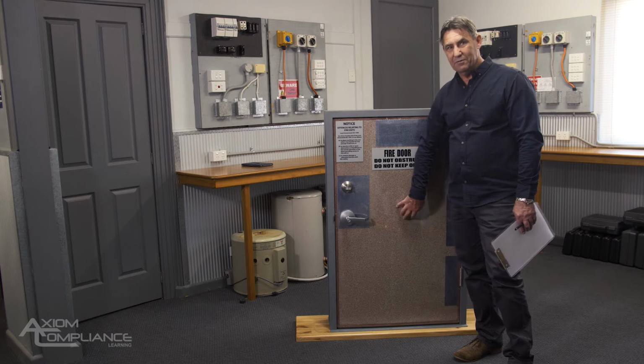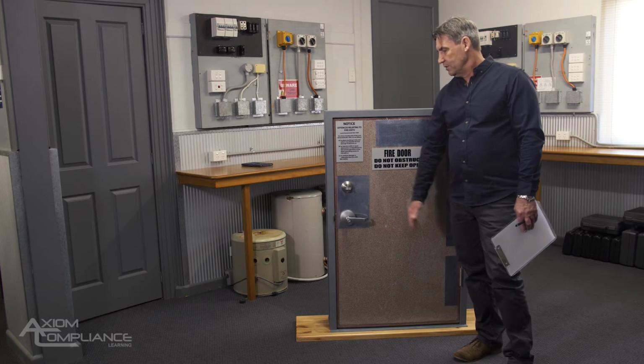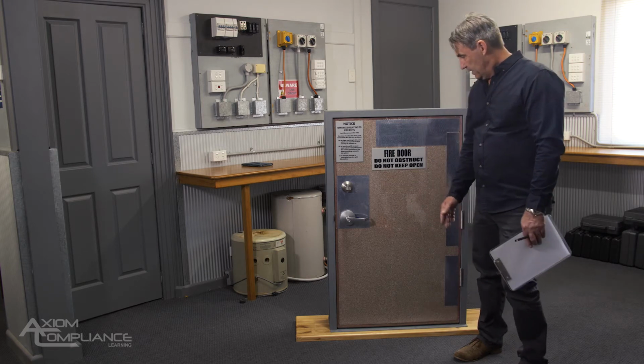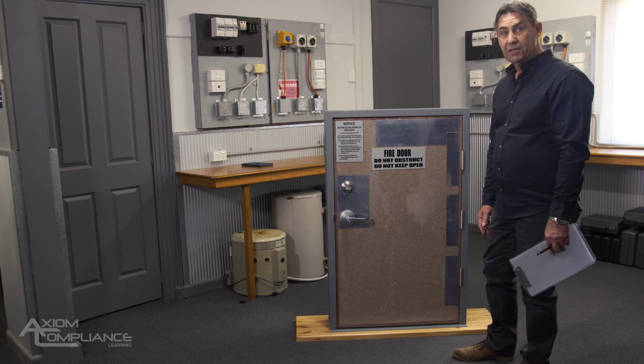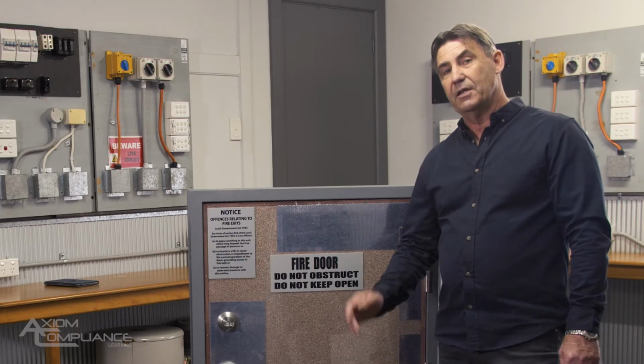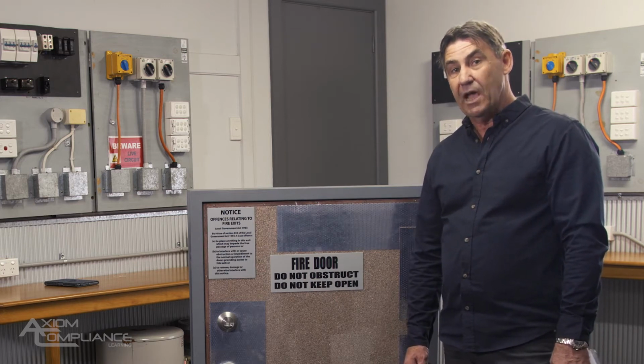It's very difficult to modify a structural door set other than putting new handles or new lock sets on. So I think this is okay. It hasn't been modified since the last inspection. The other way to prove that it's a fire door, and our second item on our checklist, is make sure it's labelled and tagged as a fire door.